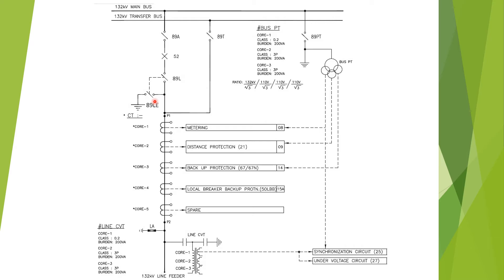Another interlocking is given from 89L. If 89L is closed — that is, 89L, 89A, and the breaker are closed — there will be voltage at this point, and in this case we cannot close the 89LE. So another interlocking is given from the 89L auxiliary contact, that is the line isolator. Again, another interlocking is given from the line CVT.